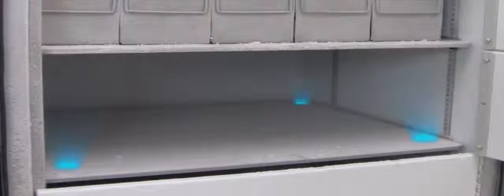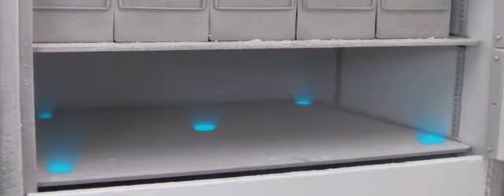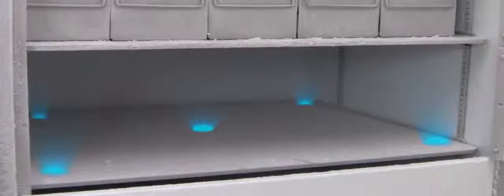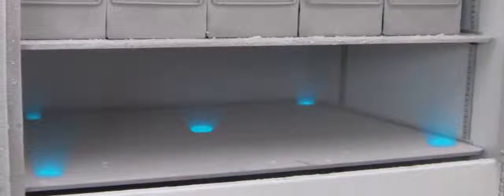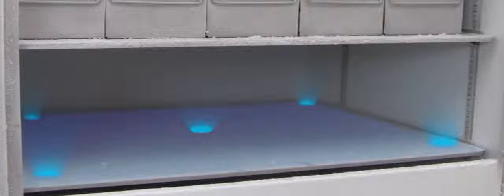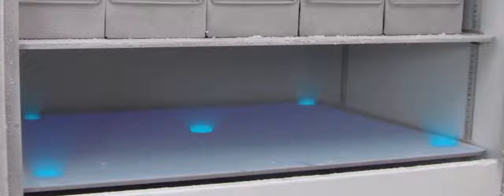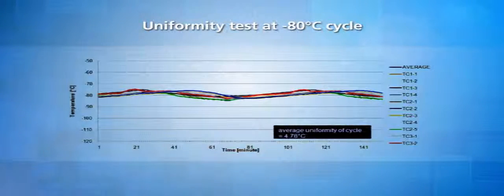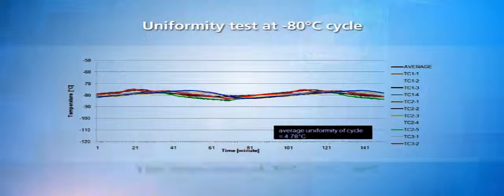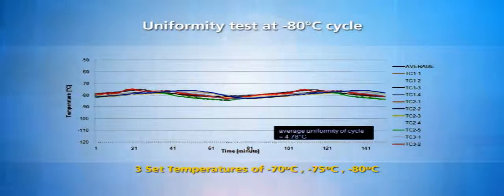Uniformity test measures the difference between the coldest spot and warmest spot in the freezer chamber when the freezer is operating at set temperature. The smaller the difference, the higher the chance that all samples are stored at the desired set temperature. A poorly designed ULT freezer may have warm spots that are 20 degrees Celsius higher than the cold spots. Esco ULT freezer can achieve excellent uniformity of less than 5 degrees Celsius at 3 set temperatures under factory test conditions.